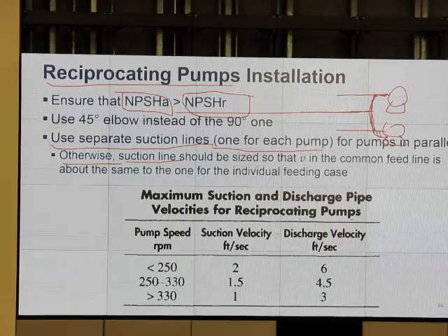When we use a PD pump, it takes a constant volume in, regardless of viscosity, right? So if we have two, it takes double. It is forced to take double. Not like a centrifugal pump. A centrifugal pump takes as much as it can push out, right? It can even flow against a dead end, but not PD.